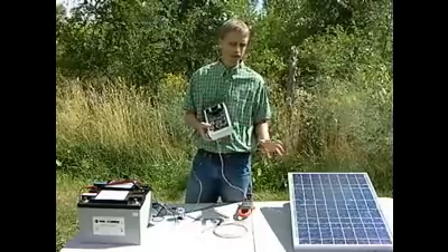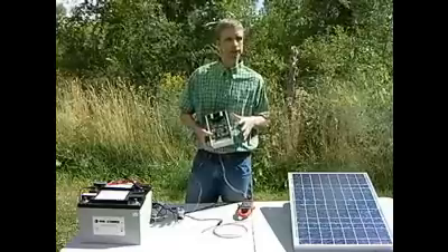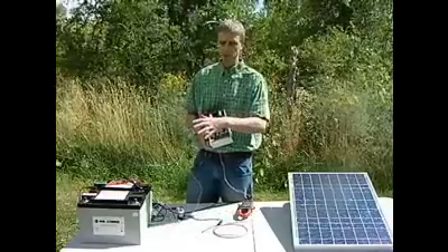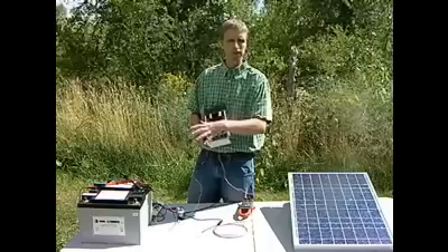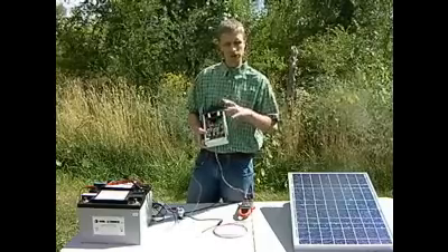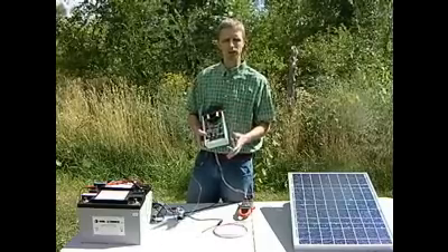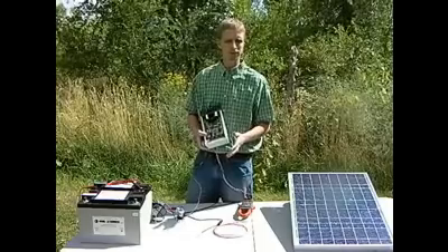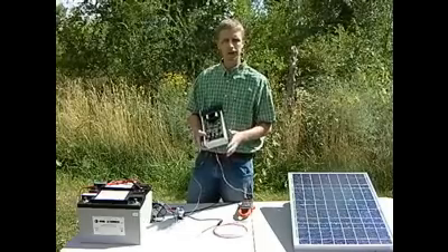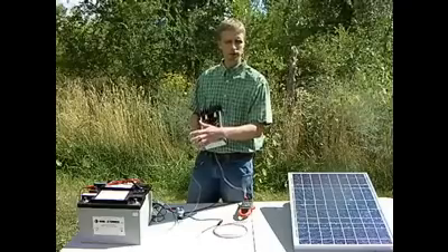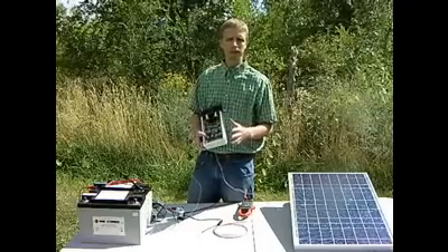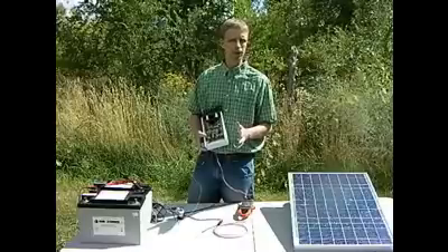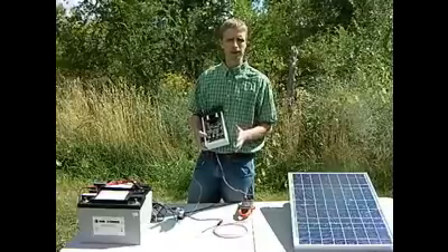This will only happen because this charge controller is a little fancier. As the battery voltage gets up to the high 13 volts, it's going to start slowly tapering down the charge. Then when it gets to 14 volts, it's going to turn it totally off so our batteries don't get overcharged. Now, there is one situation where you might want your batteries to get slightly overcharged, and that's after you've been using them for a while.